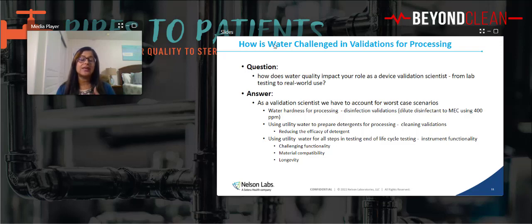And we drop it down to the MEC, minimum effective concentration. This is where you dip your test strips, and when you pull it out, it failed—you can no longer use it anymore. We're just right above that concentration, and that's what we're exposing the devices to for high-level disinfection validations. So we are taking it to the worst extreme case to do these validations.